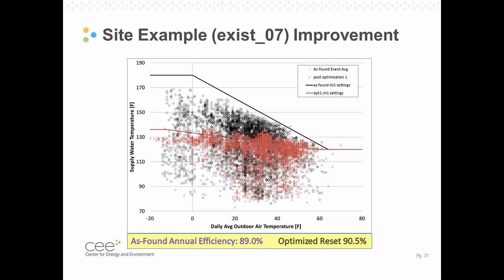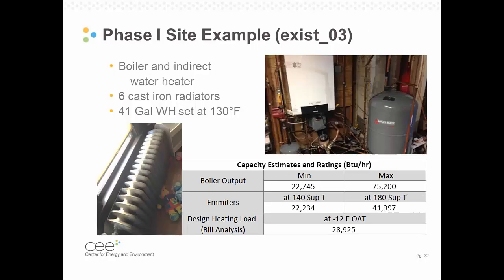And so what you can see is that we made a big change in the reset curve, and we got some pretty good reduction in supply water temperatures of some cycles. But what you can see a little bit here is how the intensity of those heating cycles is really in the middle of this plot, and that the change, or the delta T, in supply water temperature is smaller than it is at the extremes down at negative 20. And so what ends up happening is that this total annual impact is actually not as strong as you might expect. So at this site, we saw about a 1.5 annual space heating improvement, which is a pretty small improvement for the few hours that it took to optimize in the site-specific walkthrough that we needed to do in order to achieve that optimization.